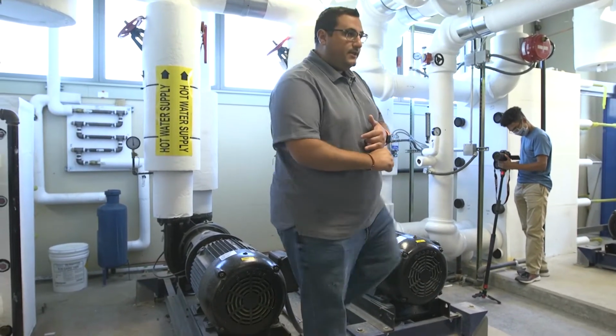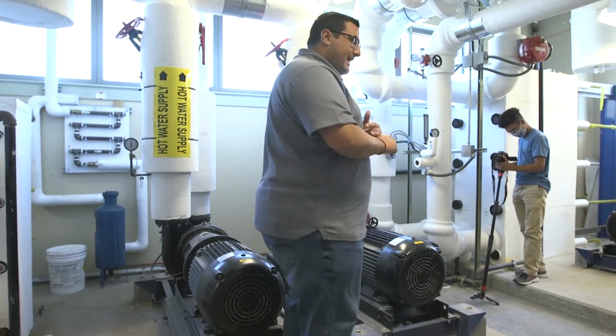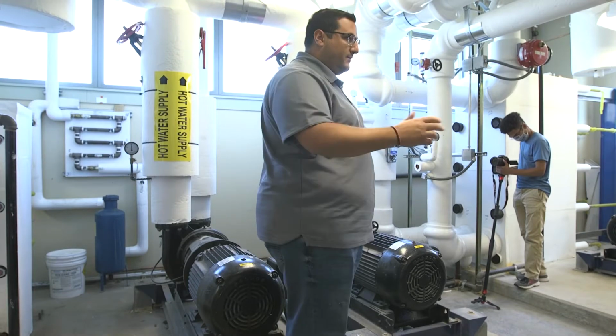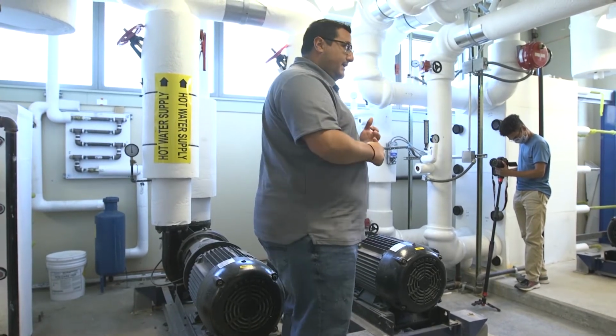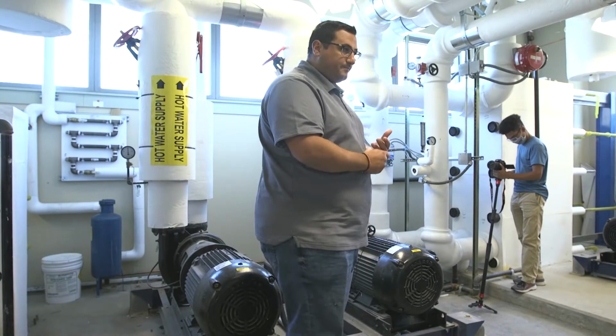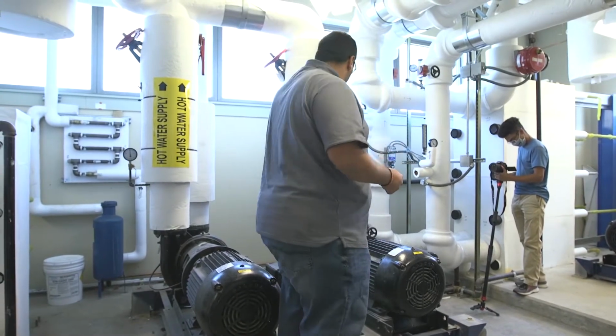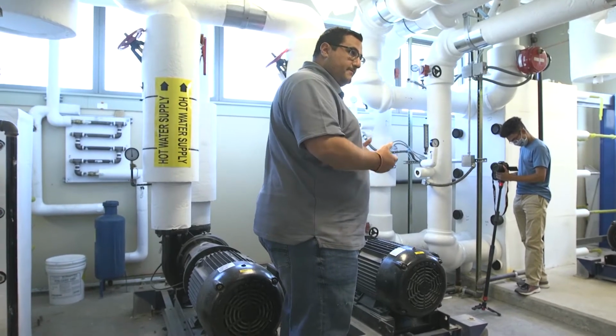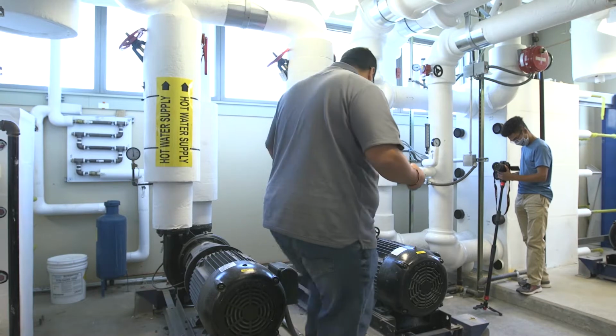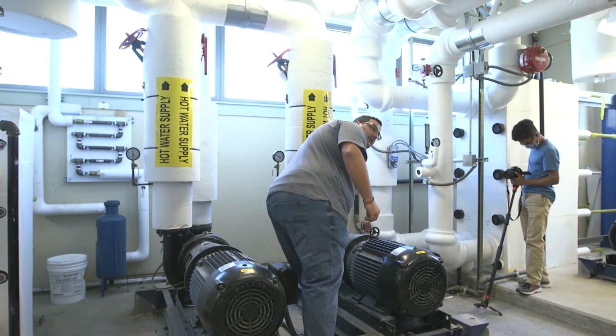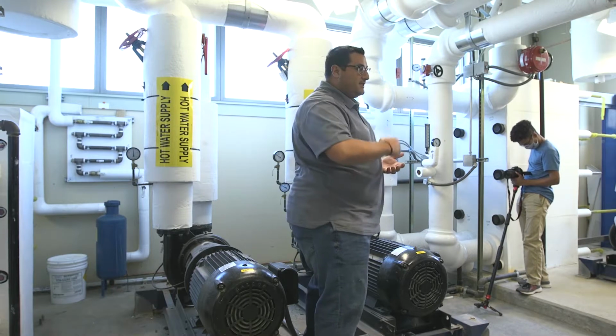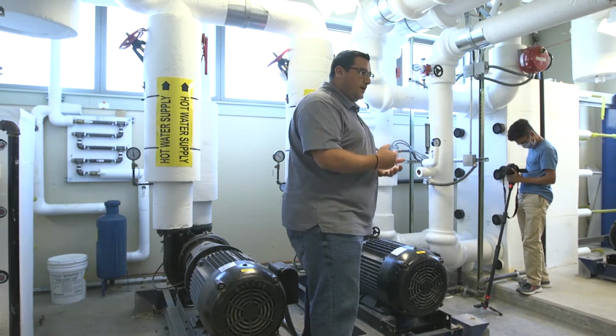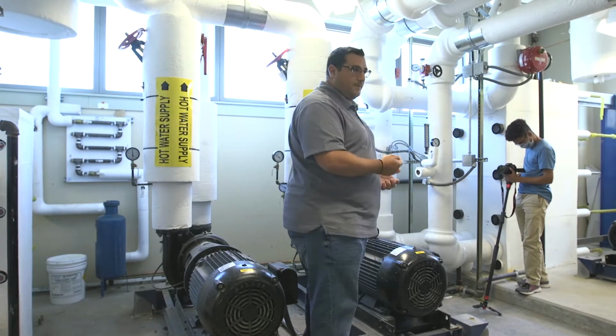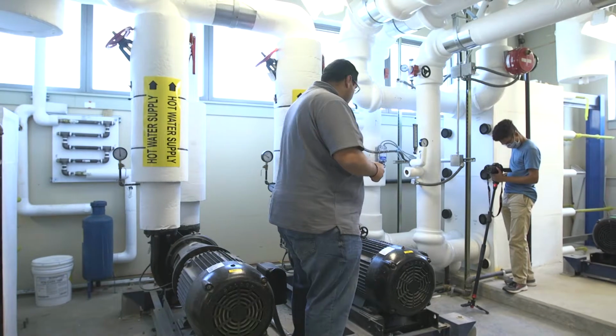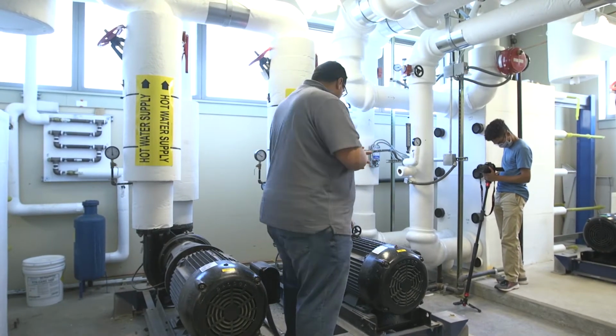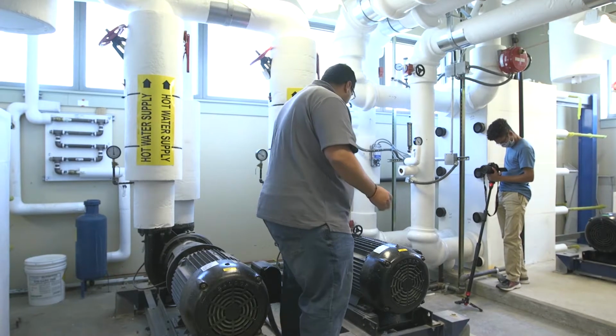Now, to start this up properly, you need to prime the pump completely. What that means is, if you need to shut down this pump for whatever reason, and you drain it and you drain the line, when you start it back up, you have to get rid of the air. So in order to do this, you open up the suction line slowly, that starts to fill up the pump, and on top here, just turn this a little bit, just enough where some air starts to escape until you get to the point of water coming out. Once you get a steady stream of water, you've filled up the pump enough. You can bump it on, make sure everything's okay, close the plug, and then your pump's primed and ready to go. So that's just starting up.